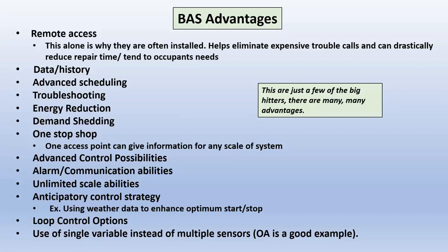That means, let's say you have 8 rooftop units that economize. Every one of them has an outdoor air sensor on it, and they're all set up to economize locally. If you take a look at those systems, half will economize, half won't. They don't come on at the same time. There's no congruency to how they operate at all. So if you use a single variable, in this case, a preferable one would be the outside air sensor, obviously, but you use a weather station grade, such as a Vaisala or something, and you control all this off of one variable. And then they all operate the same. They're all in conjunction with each other.